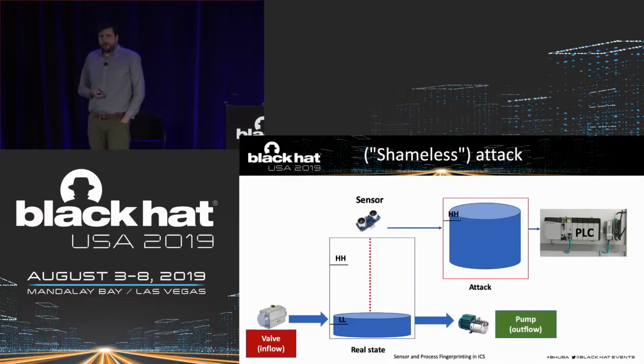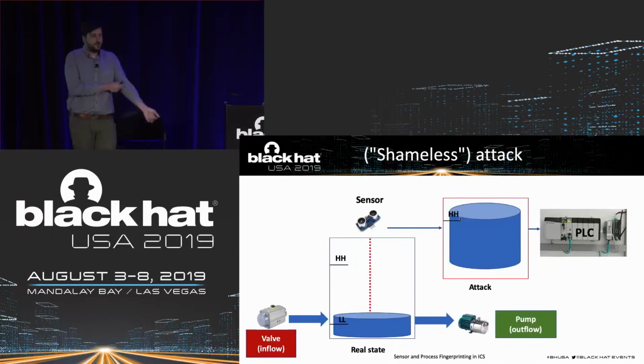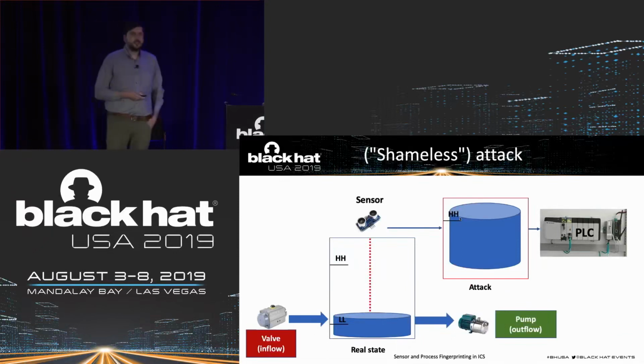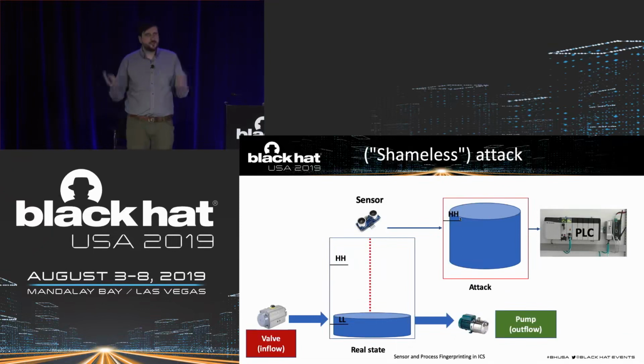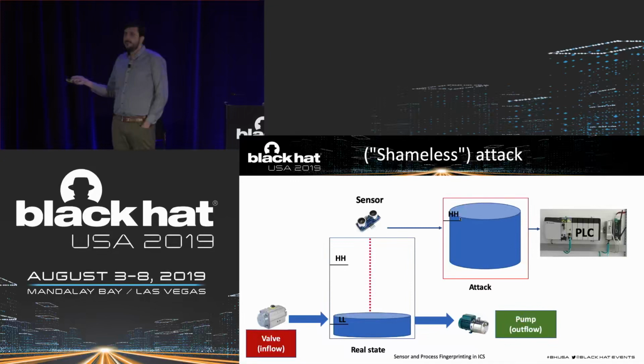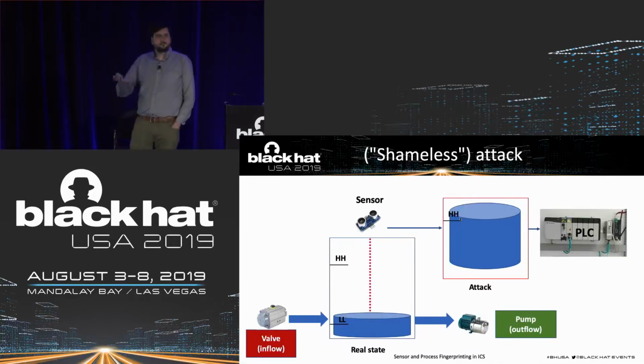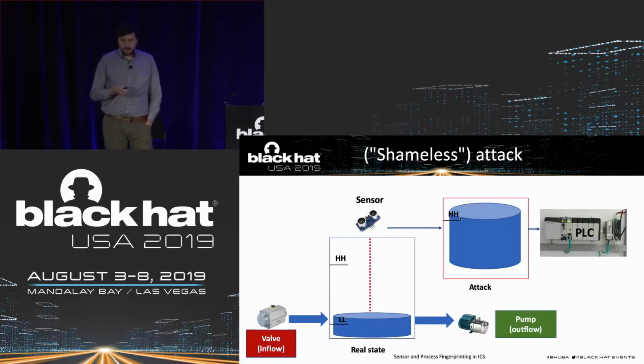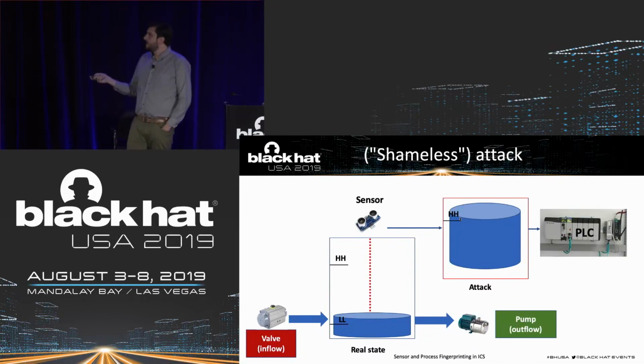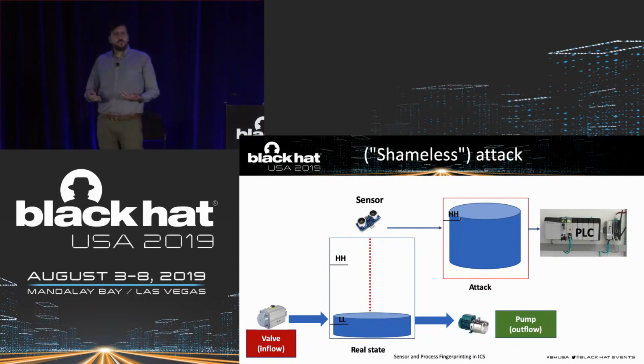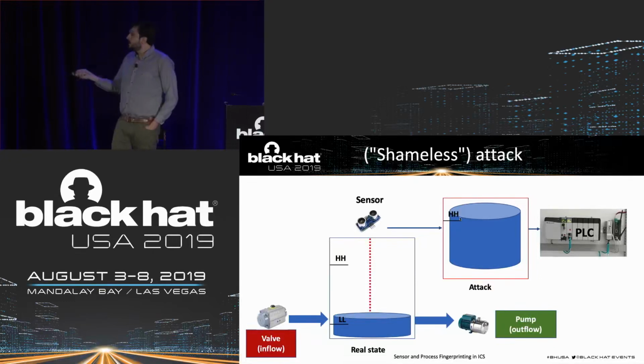So what can an attacker do concretely? Here's a first example of an attack—I'll call it shameless, just a term I coined. It's shameless because we have a tank that had a certain water level at a certain timestamp, and then the attacker breaks in and claims that water is suddenly much higher than it actually is. Because the trust model is that the PLC will trust sensor data coming from the L0 and L1 networks, it will take the wrong control decision.